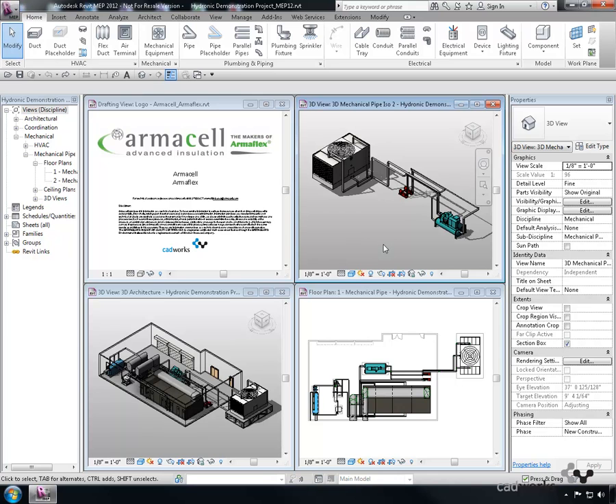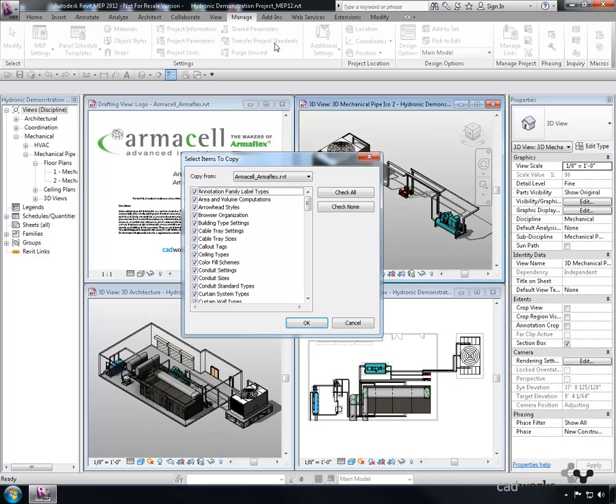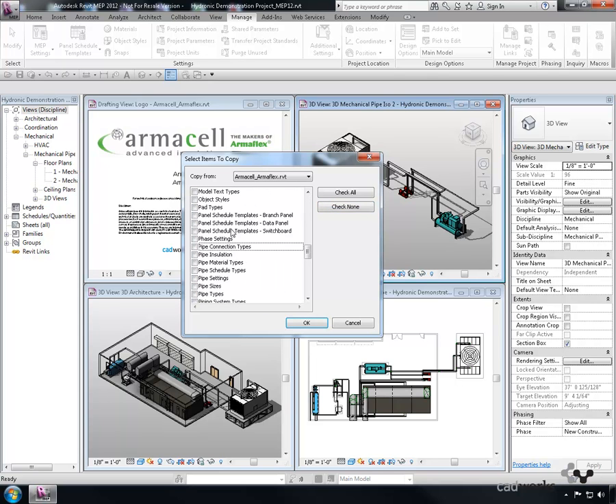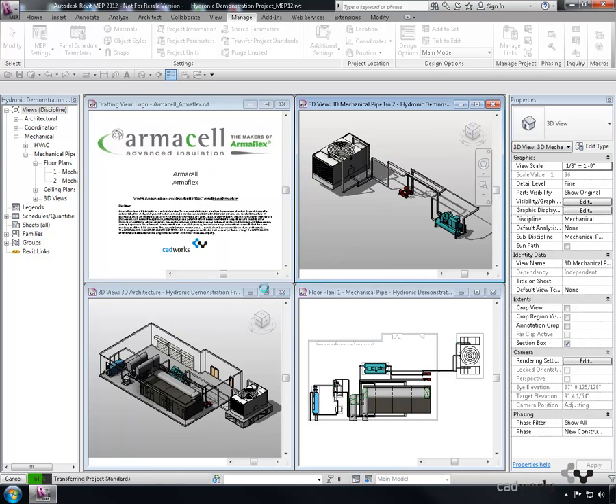Verify that the active project is the one that will have the elements transferred into it. Once verified, select Transfer Project Standards from the Manage tab. In the Select Items to Copy dialog box, select the Check None button, then check only the Pipe Insulation category. If the Duplicate Types dialog box appears, this is okay. Please select Overwrite.